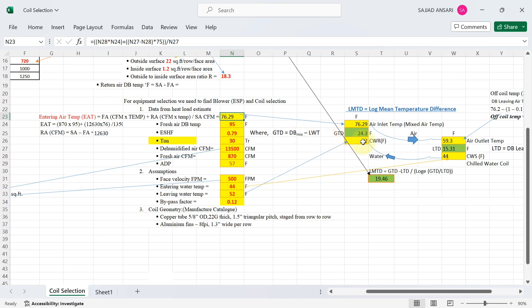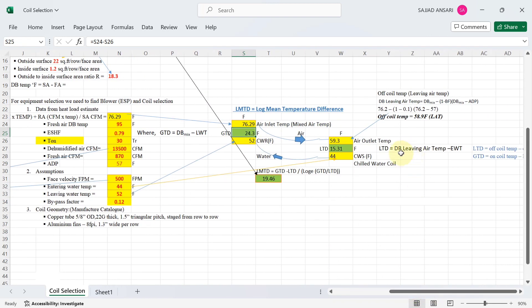With the entering air temperature (DB mix) of approximately 76.29°F and leaving water temperature of 52°F, the greatest temperature difference (GTD) is about 24.3°F. To calculate the least temperature difference (LTD), the formula is: off-coil temperature − entering water temperature. The off-coil temperature formula is: DB mix − (1 − bypass factor) × (DB mix − ADP), which gives approximately 58.9°F.